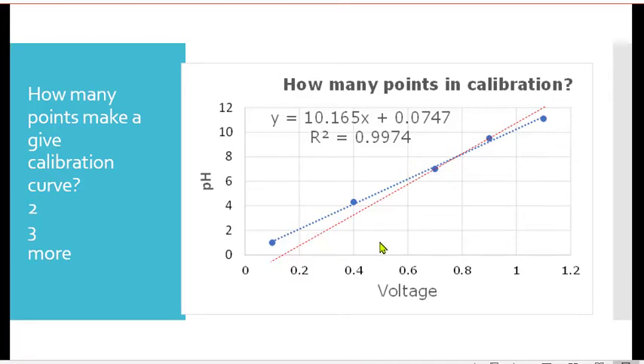Let's just try another couple points. Maybe that was just a fluke. Here's two more I took here and here, and sure enough, I've got a little bit of error. So what we learn is using just two calibration points is not acceptable because you're probably going to have pretty large error.